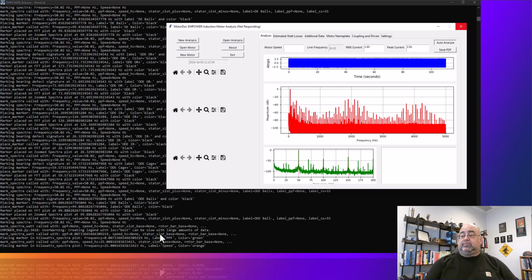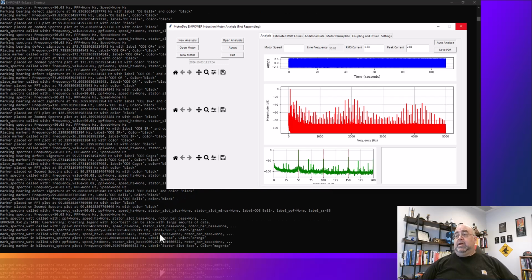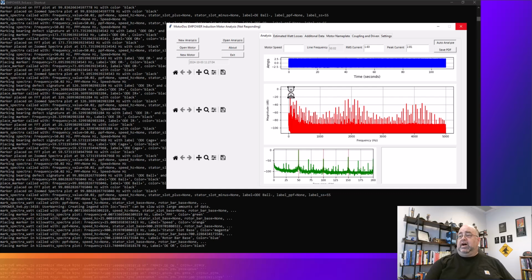Now you notice these humps here - that's an inverter, a 2 kilohertz setting on the inverter. This down here is the line frequency - that'll be 50 hertz for this one, 50.02 actually. And it's going to calculate the running speed for me.